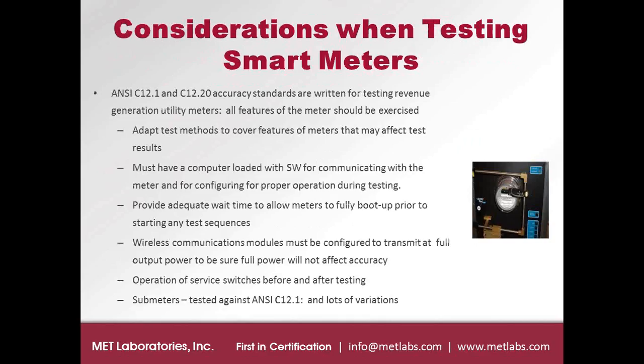So the ANSI documents are really written for revenue generation utility meters, socket meters, A-base meters. And when we're looking at a test program, we want to make sure that all the features of the meter are exercised properly, so that everything's covered in the report, and there's no question about, well, was the AMI module transmitting at full power, that sort of thing. It'll all be in there.